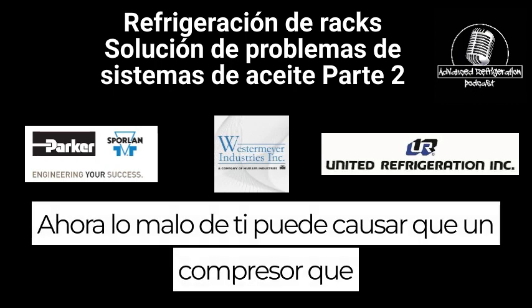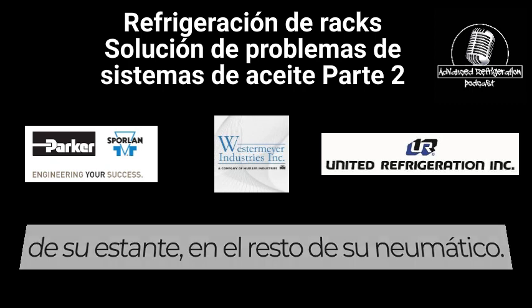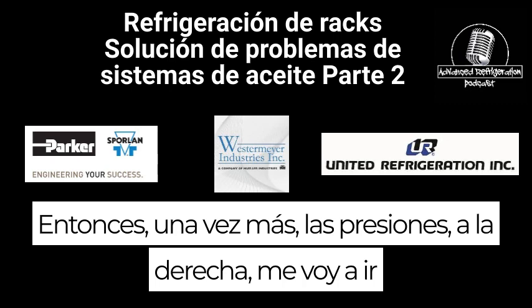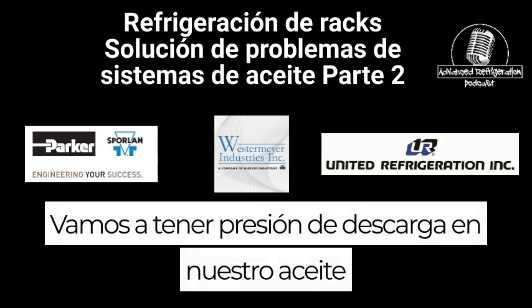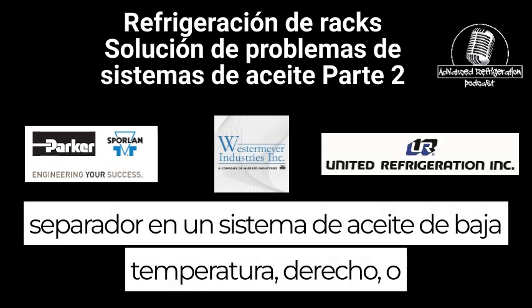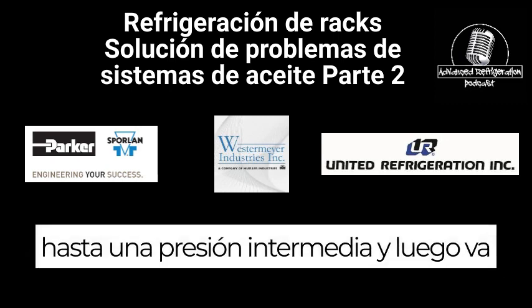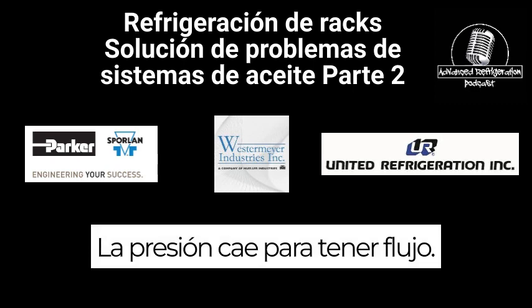Now the bad thing about it is that one compressor that has piston valve issues can cause oil failures on the rest of your rack, on the rest of your side. So once again, I'm going to go back to the pressures. I'm going to go over this again until I'm blue in the face. We're going to have discharge pressure on our oil separator on a low temp oil system, or low pressure oil system. Then it's going to go down to an intermediate pressure, and then it's going to go down to the crankcase pressure. You need the pressure drops in order to have flow.